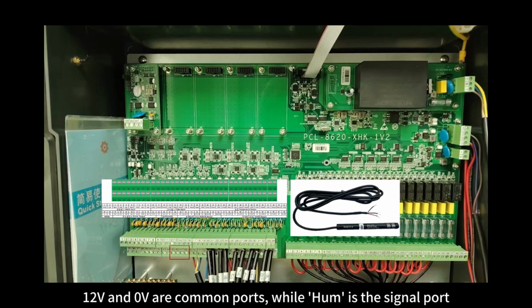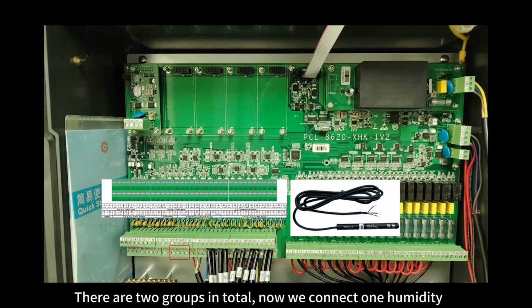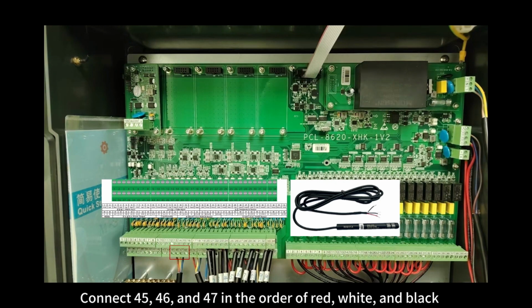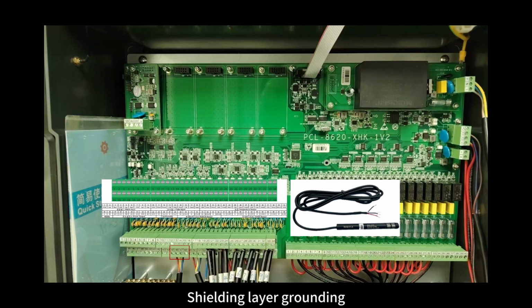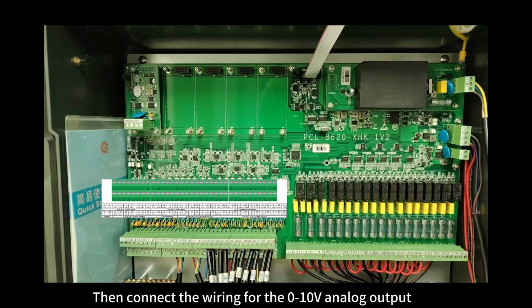12 volts and 0 volts are common ports. 'Hum' is the signal port. There are 2 groups in total. Now we connect 1 humidity. Connect 45, 46, and 47 in the order of red, white, and black. Shielding layer grounding. Then connect the wiring for the 0 to 10V analog output.